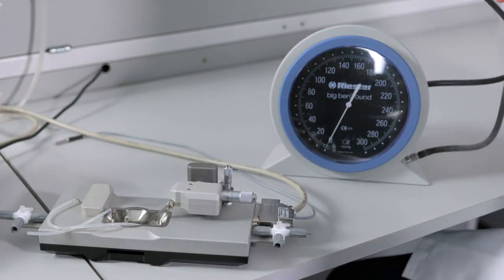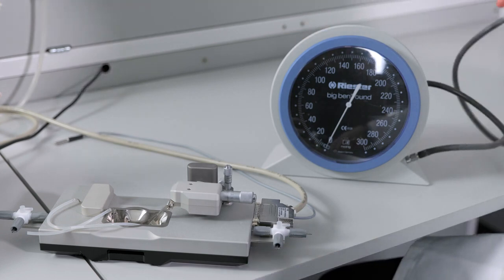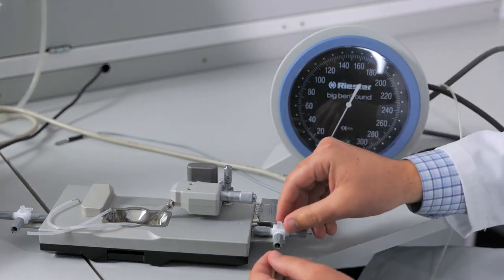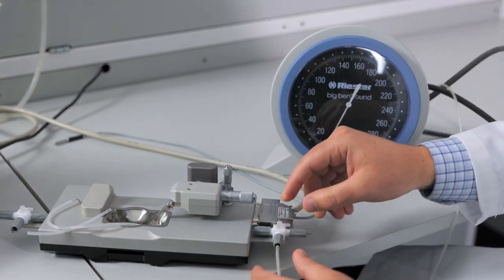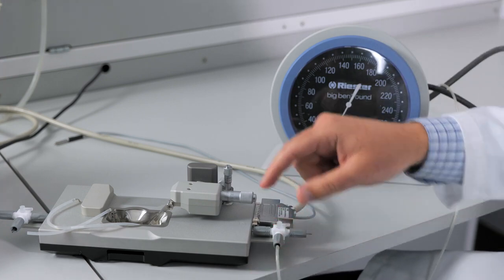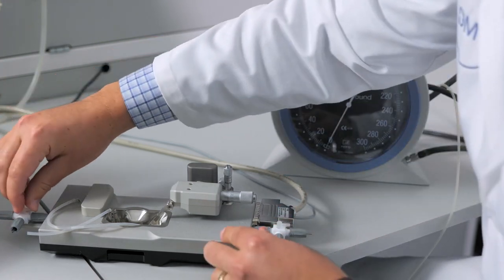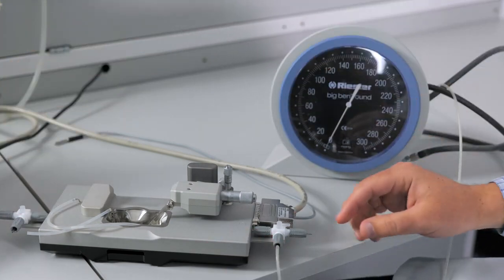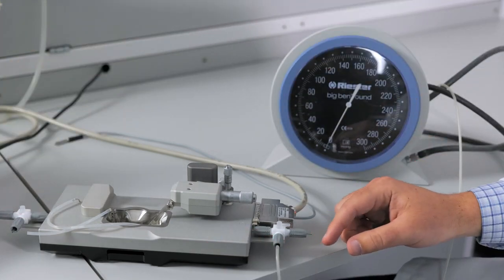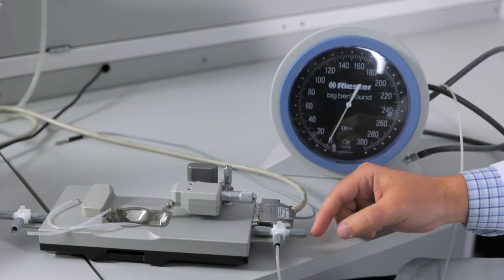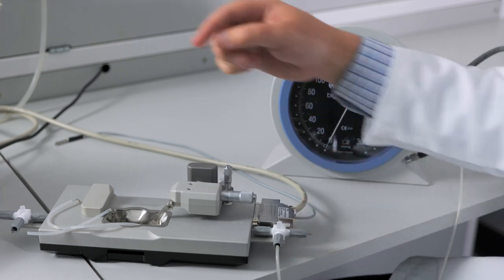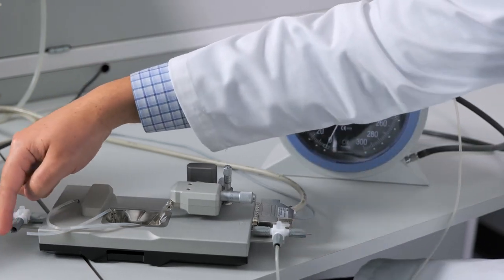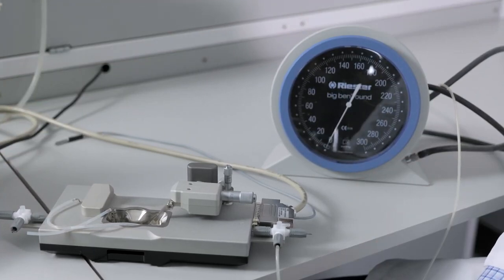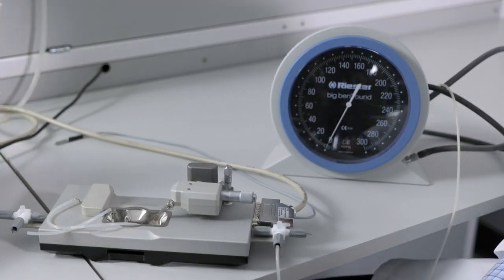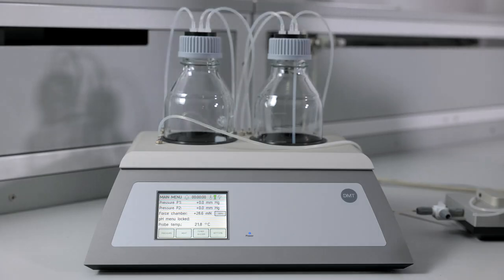We then need to connect our pressure manometer to the right side three-way valve and make sure that your three-way valves are pointing in the correct direction to ensure that you don't have any pressure leak. On the right side, we have our open port closed. On the left side, we have the bottom port, which is open, also closed. We can then begin the pressure calibration.